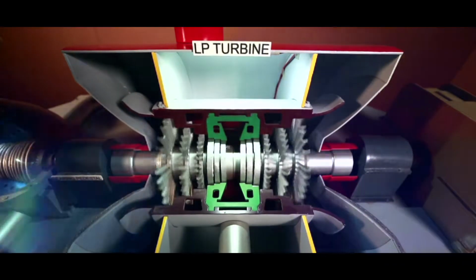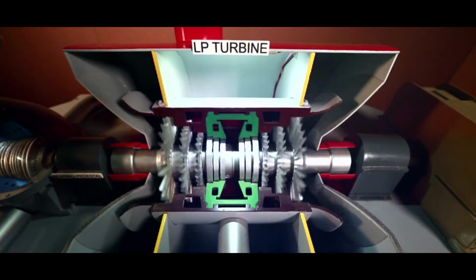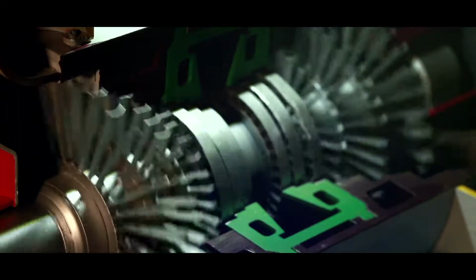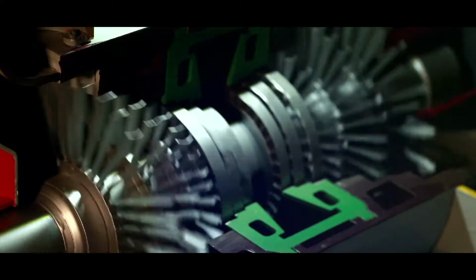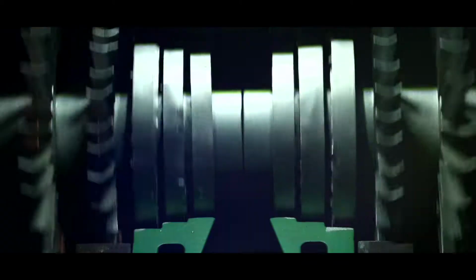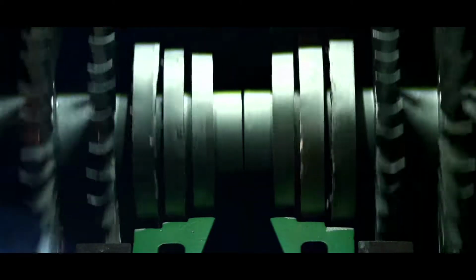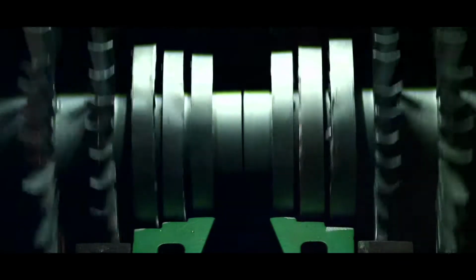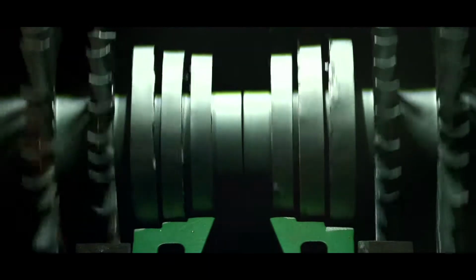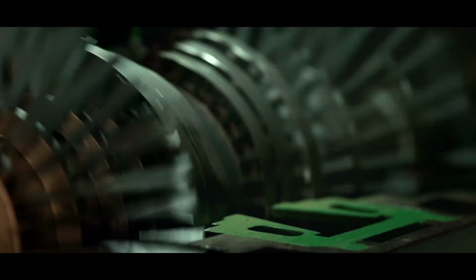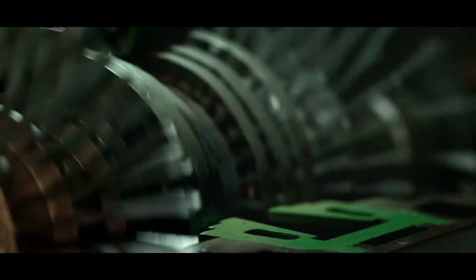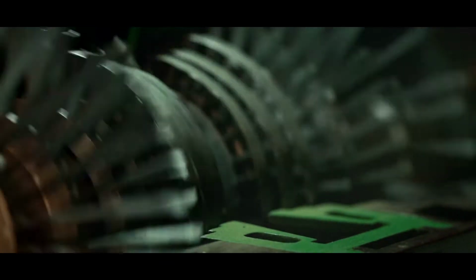Lastly comes the low pressure turbine or the LP turbine. The casing here is a triple shell design, the shells being horizontally split and welded rigidly. The innermost shell, which carries the first three rows of the blade stages, does however have mobility to account for thermal expansion.